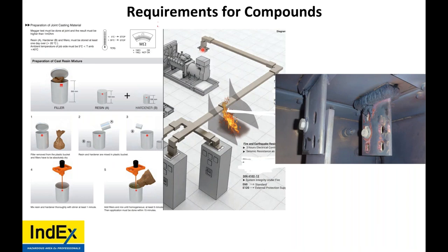If you don't do things correctly, somebody may say the number of bolts doesn't have to do with hazardous areas, it's an electrical requirement. The mechanical completion requires a detailed inspection. That inspector is an EX inspector. If he did not point this out, or at the time he inspected it, it was there, and then things changed, the whole point of verification and validation, pictures and documents, is to see what, how, why, and where something happened. Because someone will always try to blame the person at the bottom. It was obviously the inspector's fault. Take pictures, cover your behinds.